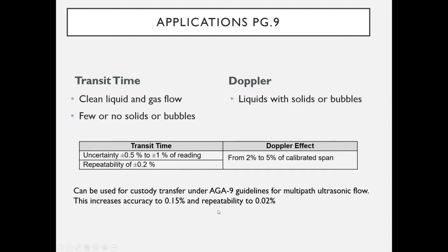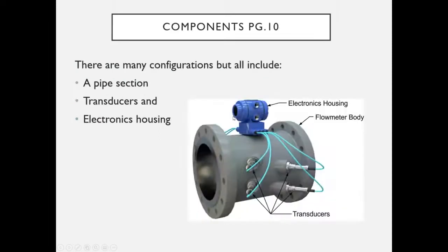Using the multi-path approach gives a significant accuracy advantage. Doppler accuracy is far less precise, ranging 2–5% of calibrated span. Looking at the components of an ultrasonic transmitter: most configurations include some form of pipe section or spool, transducers or transmitters and receivers that send and receive ultrasonic pulses, and an electronics housing with display and configuration interface for utilizing the signals from the sensors.